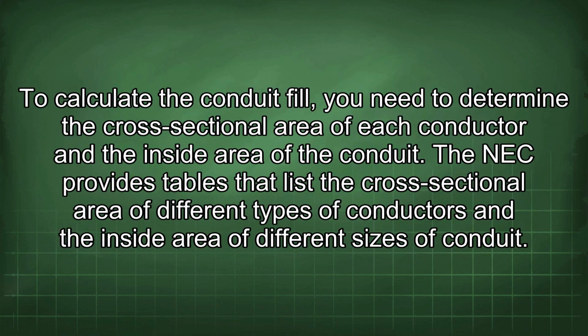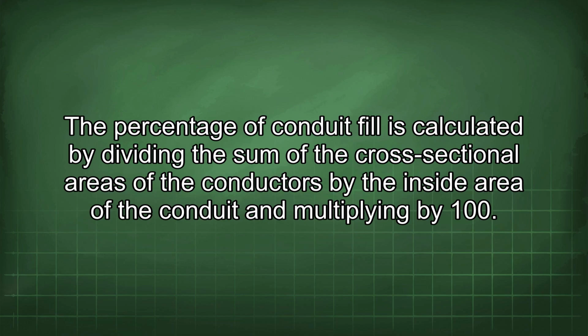To calculate the conduit fill, you need to determine the cross-sectional area of each conductor and the inside area of the conduit. The NEC provides tables that list the cross-sectional area of different types of conductors and the inside area of different sizes of conduit. The percentage of conduit fill is calculated by dividing the sum of the cross-sectional areas of the conductors by the inside area of the conduit and multiplying by 100.